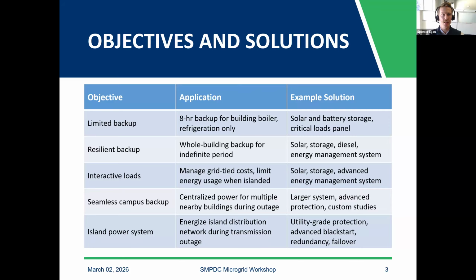In those last two use cases, having those different voltage levels means you also have transformers in the system, and you might have much larger loads, like large motors. Motors and transformers are two types of equipment that are especially challenging in microgrid design because they have a much larger power requirement.